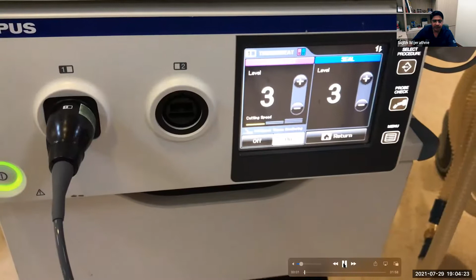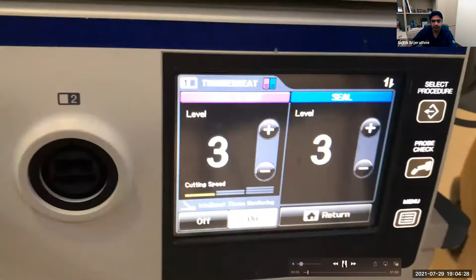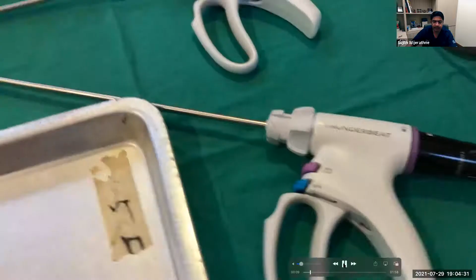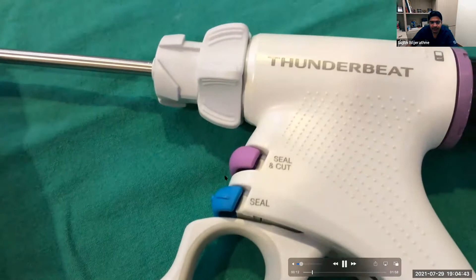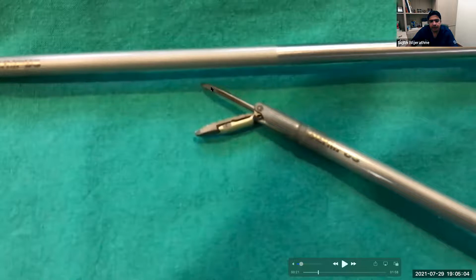What you see here is a combined device which uses both ultrasonic as well as high frequency bipolar energy. This is called Thunderbeat, by Olympus. You have two main buttons to use. Your ultrasonic energy is used for seal and cut, and for pure seal, we use advanced high frequency bipolar. This is the oscillating jaw, and for bipolar, there's a metal component here that will complete the tissue effect for bipolar energy.